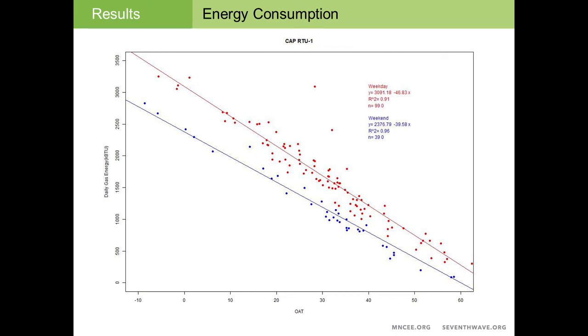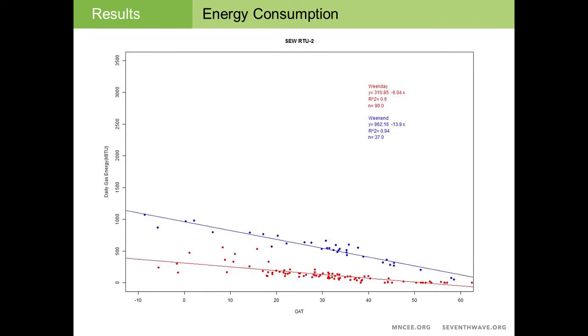This is a very clean gas graph, where the red lines are the energy consumption during the weekday period and the energy consumption in the weekend period. You'll see that the R squared is very good. It's around 90% or better for both, so I consider this to be a very good gas model. Conversely, we have another site where just the opposite is happening: weekend consumption is actually higher than weekday consumption. That could be attributed to the fact that the space has heat requirements that won't be met without the people or the activity in the space.